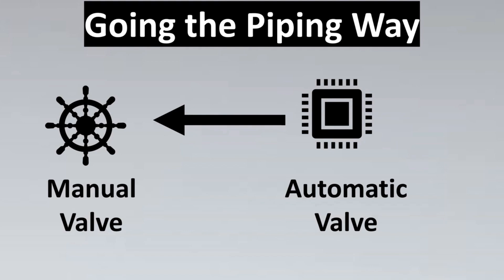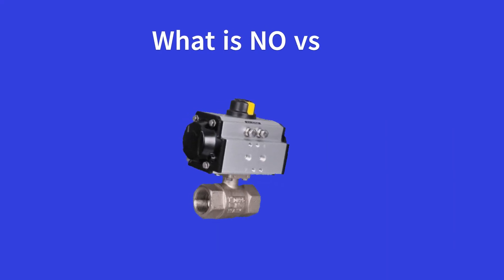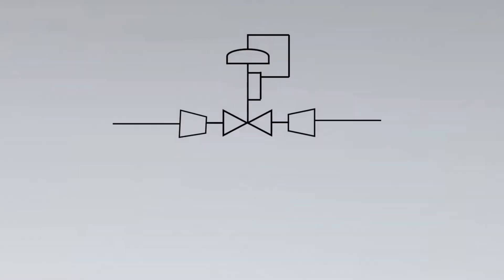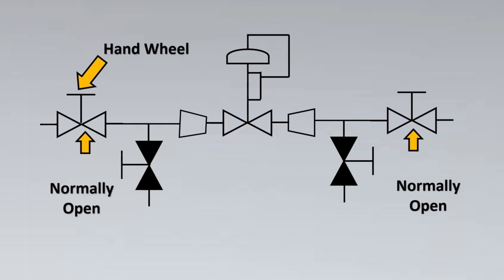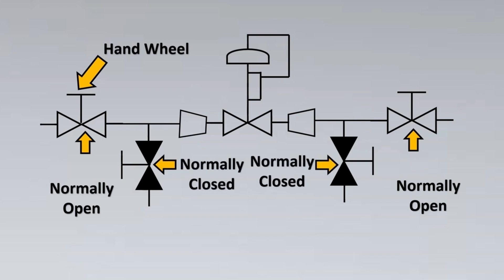Now let's understand NO/NC valves. Here are four valve configurations — from their symbols, we can see these are hand-wheel operated valves. In a P&ID, if valves are not colored, it means they are Normally Open (NO); if they are colored, they are Normally Closed (NC). So just by color, we can identify normally open and normally closed valves.